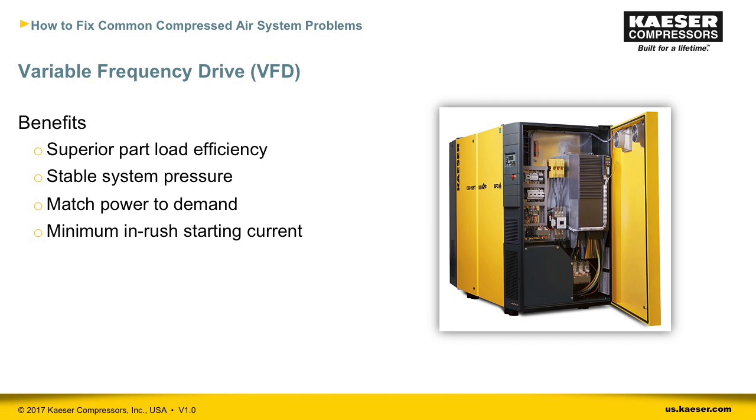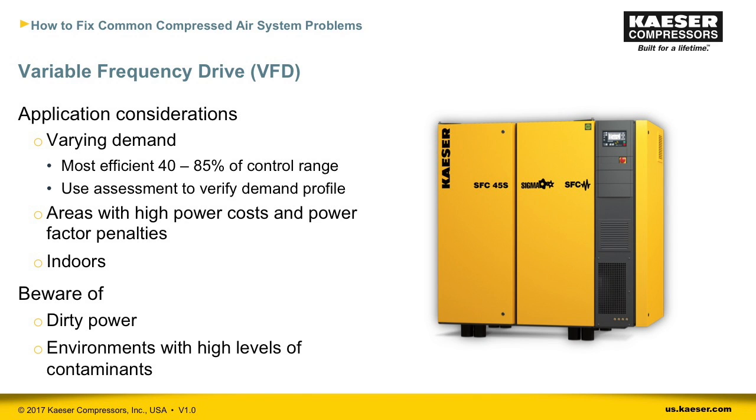VFDs can deliver significant energy savings, but please note that these savings will only happen if it is properly applied. Here are some tips for properly applying a VFD. This type of compressor is designed to handle varying demand. If the demand to meet your production needs is consistent, you won't get the energy saving benefits. I recommend you get a proper compressed air system assessment like Neil discussed earlier to understand how exactly your demand varies. Also, if you have high power costs and/or power factor penalties, then a VFD might be a good choice.